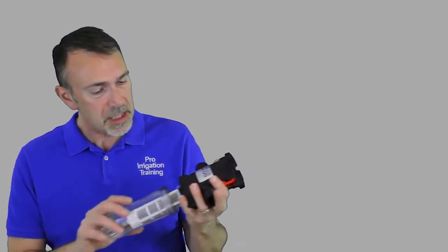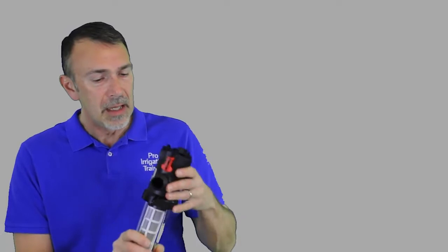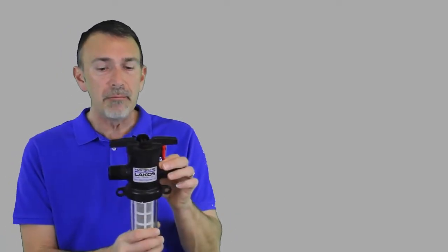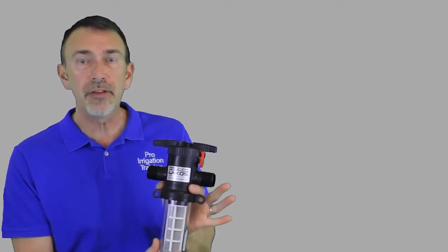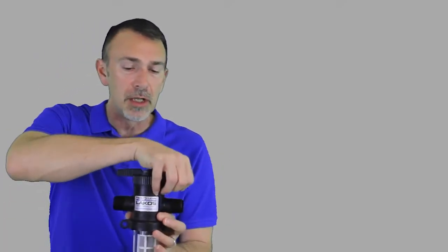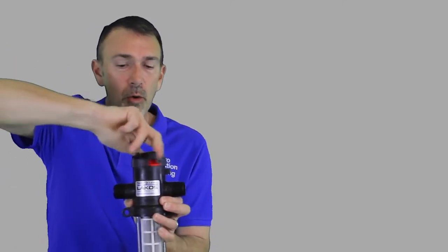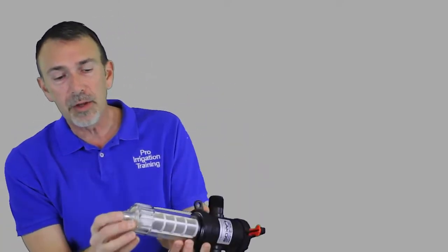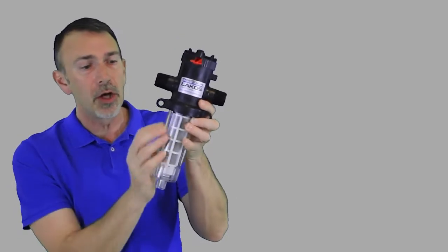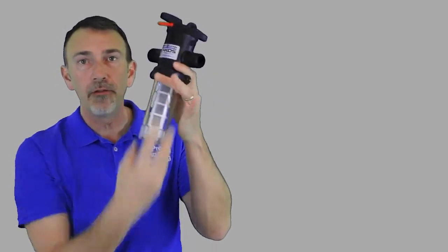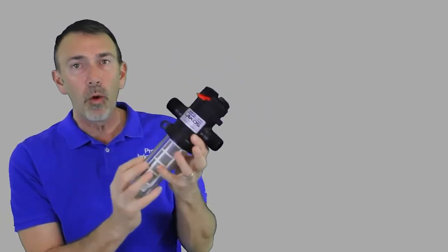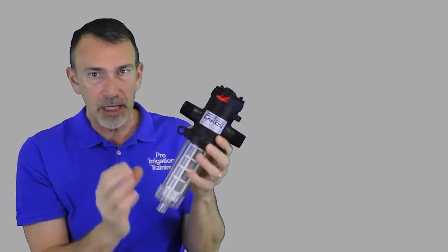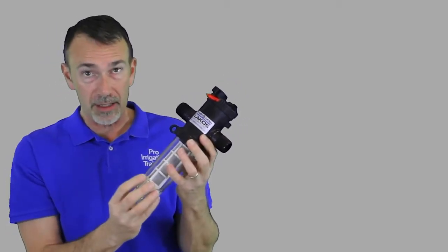And several different manufacturers offer optional screen sizes with it. So let's put this back together here. Make sure this is sealed up nicely. And they like this one to be mounted in a vertical position. And what happens is that the twist to clean feature on this, so what happens is you just flip up this little lever here and to flush it, it's a quarter turn clockwise. And what it does is it withdraws this from the little fitting here and will flush it out because all of the particles are on the outside. It'll flush all of this stuff out through here. The way that this one works is the water comes and then goes in through the filter and out. So it's easy to flush the particles off the outside.